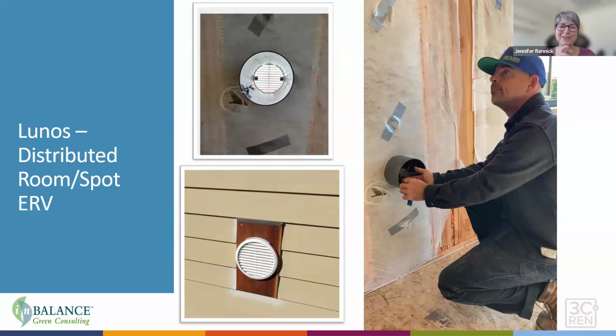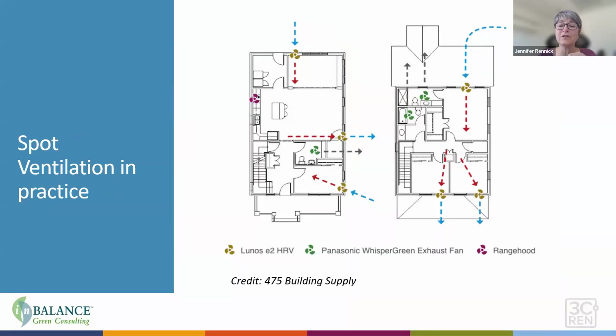But there's a small fan and a ceramic core, and these work in pairs, connected with a low voltage line to a controller. As one set of fans turns on, it pulls air in while the other set turns on and exhausts air. Then it reverses, so the heat exchanger heats up as airflow moves one way. In heating mode, as exhaust air is sent out of the house, it heats up the ceramic core. When the fan reverses, cold air comes in but it's preheated by that ceramic core as it passes through, providing ventilation to the house.